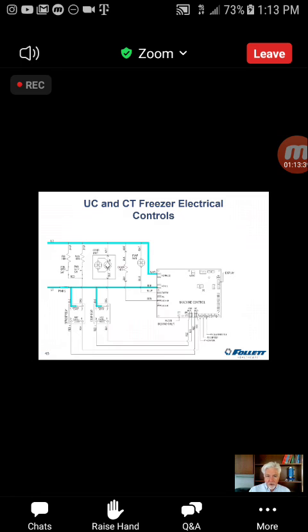So under counter and countertop freezer controls, we're going to the freezer now. We've got a few extra components that we have to add. First off, we have a second relay, all right? The second relay is what provides power for those defrost heaters that are on the unit during the defrost cycle. So on under-counter units, we have a defrost heater on the face of the coil, and we have a separate lower wattage one in the drain pan.